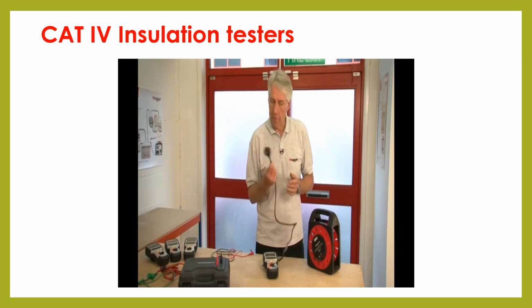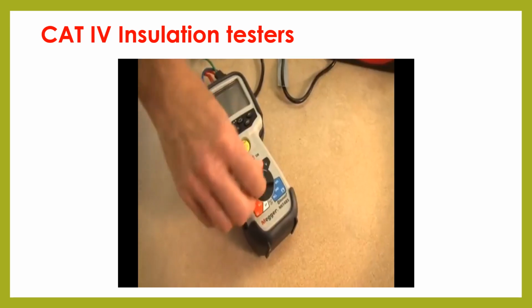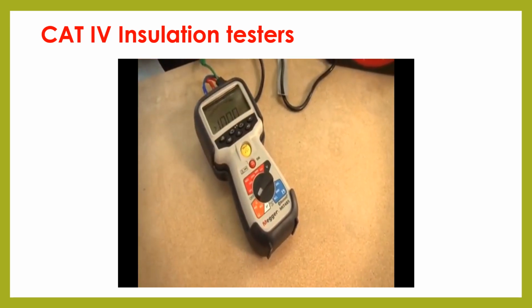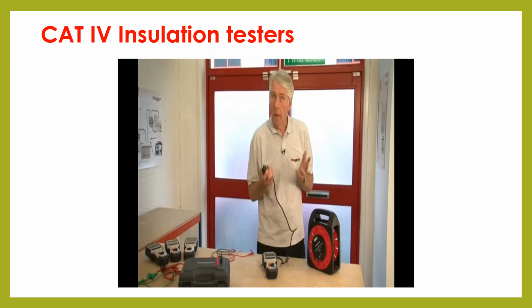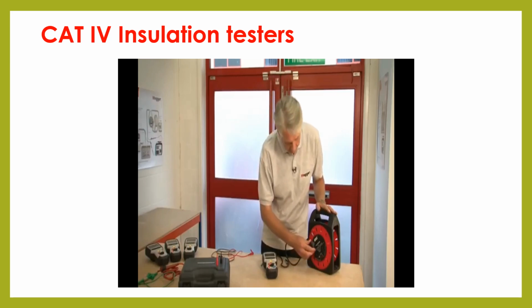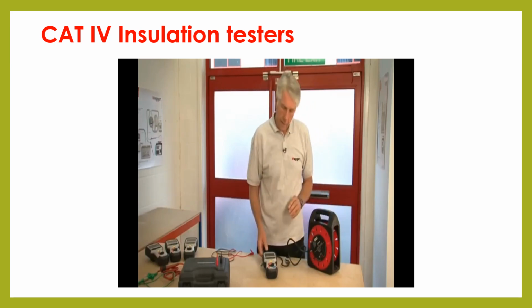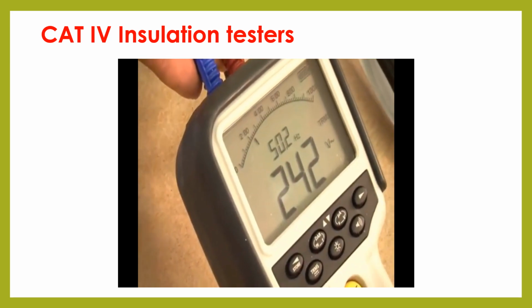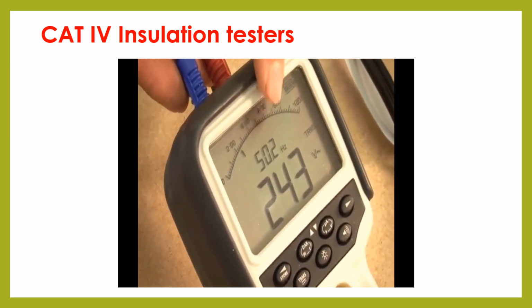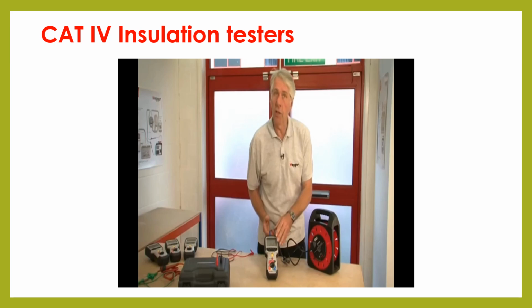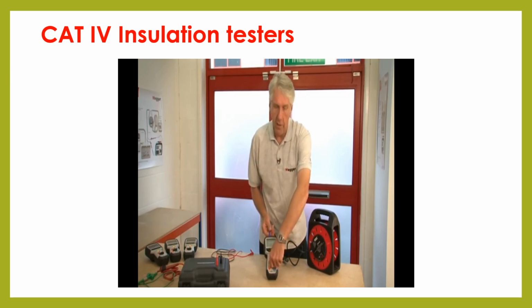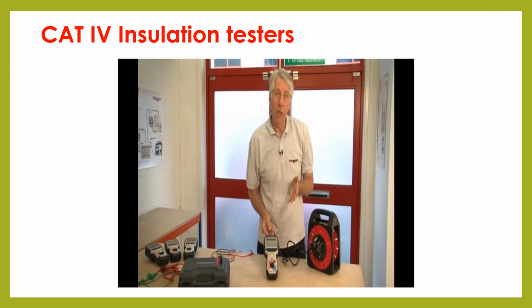So here I have a mains lead which is connected to the device. Let's switch it to continuity range. It will read open circuit. I'm now going to simply plug it into the mains. Now you'll see that the product immediately warns you of a live voltage by repeatedly sounding the buzzer, and it automatically changes to a voltage range showing the actual voltage that's present. Now I can push the test button, I can select different ranges, and it will not damage the instrument, and more importantly, it won't damage you.